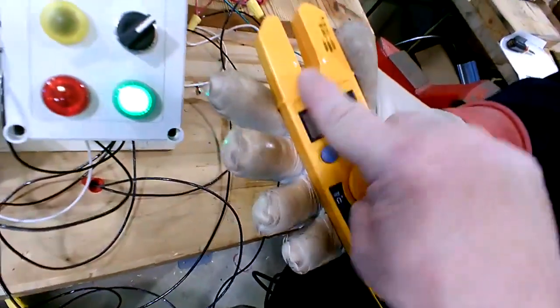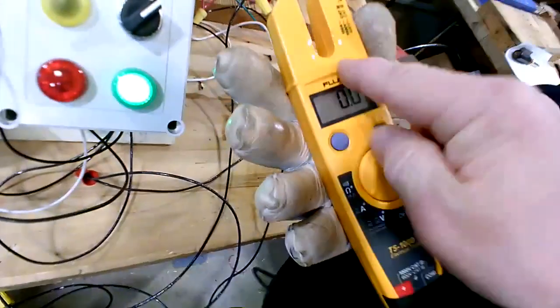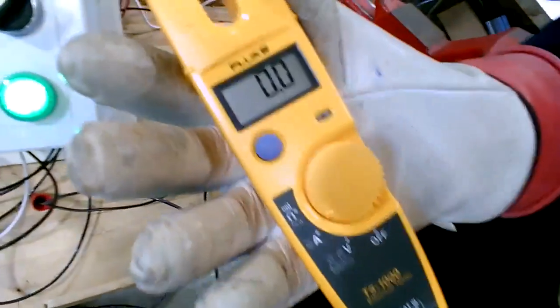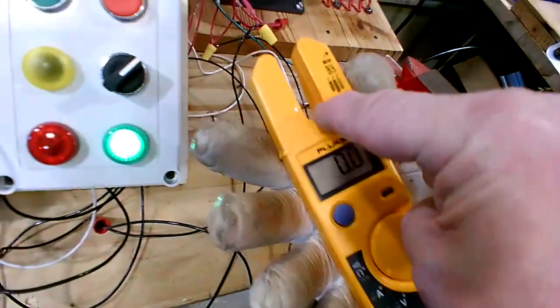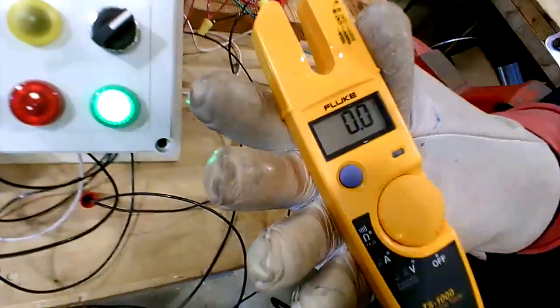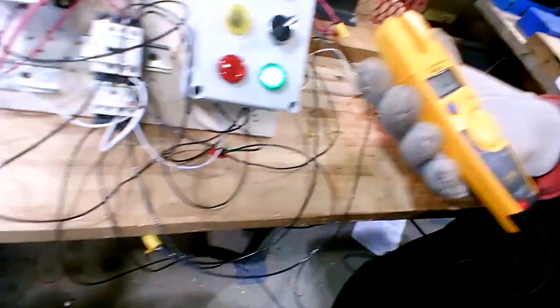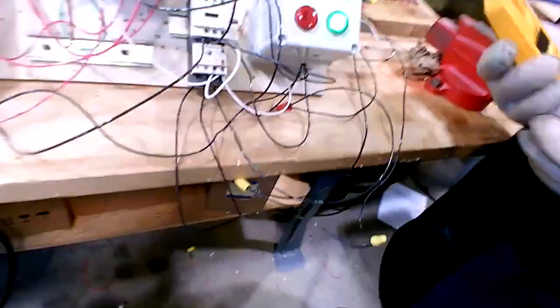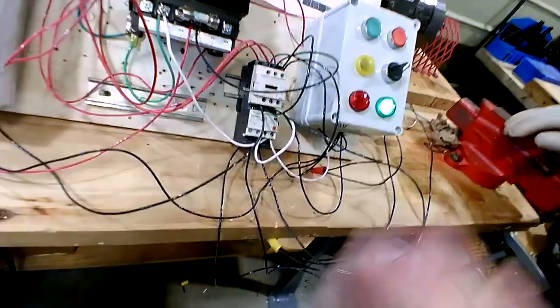The idea about an open fork clamp is you got to get in there where the lines are on the plastic. Those dash lines, you got to get the wire in that sensing area for it to give you an accurate number. If that wire's up at the tip, it's not as accurate as it is down here. Now, with a closed jaw clamping around the wire, it doesn't matter where it's at in the clamp. They're more forgiving. So you're set.